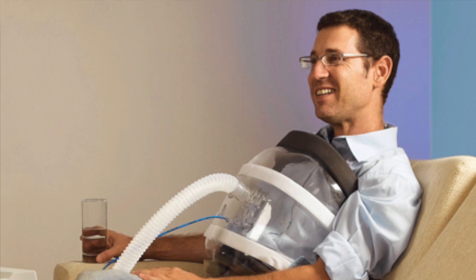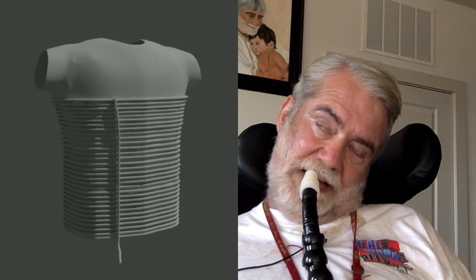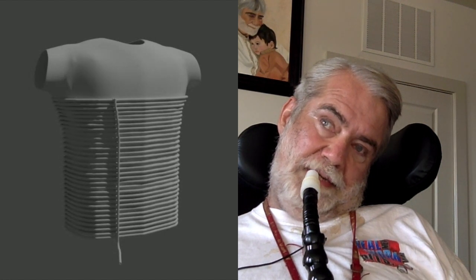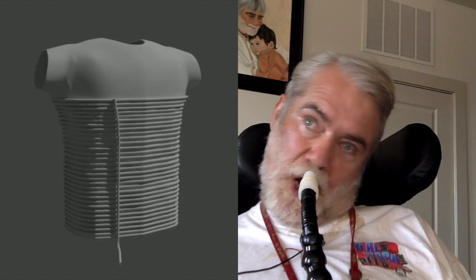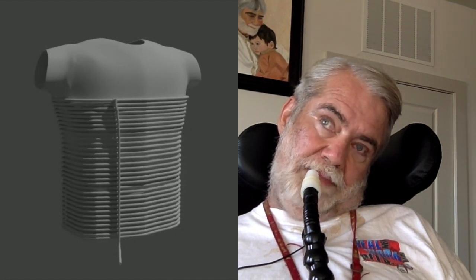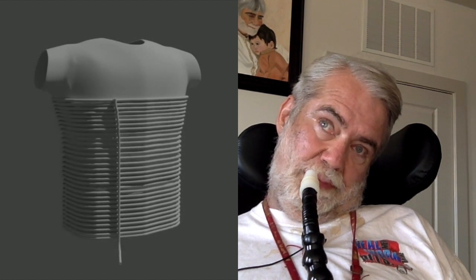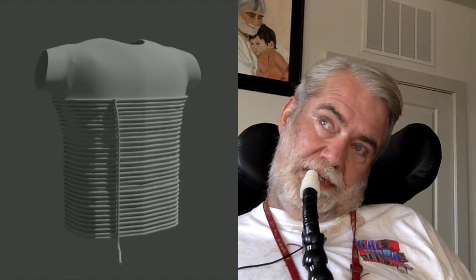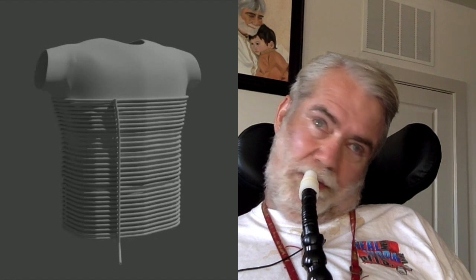It's basically just a much smaller shell than the iron lung. And in my ventilator, there is a flexible, expandable vest around your chest. The adhesion between the vest and your chest is because of a low and constant vacuum surrounding your torso. In the Hayek cuirass ventilator, the zone around your chest varies from vacuum to pressure, and there are foam seals between this rigid shell, which kind of resembles a tortoise shell around your body.